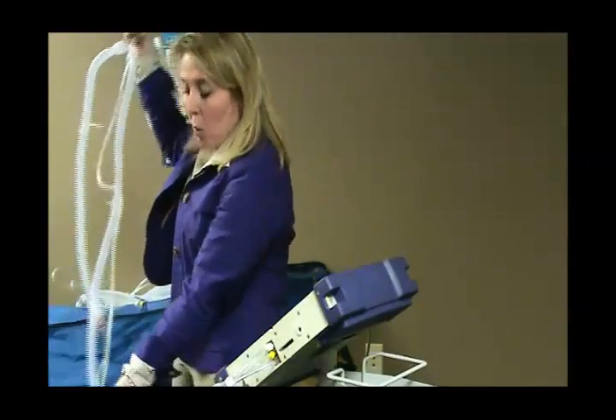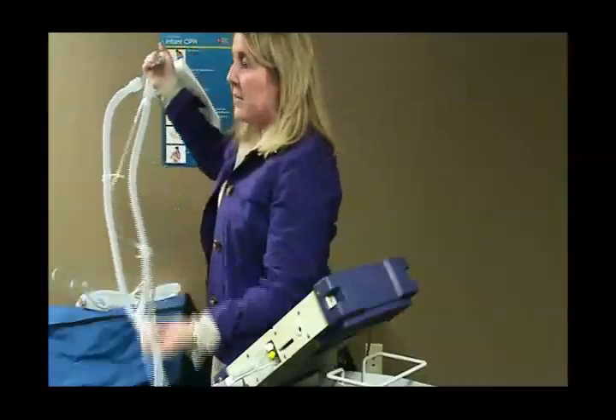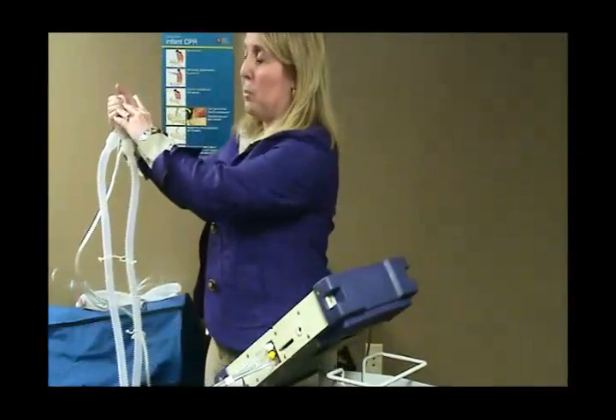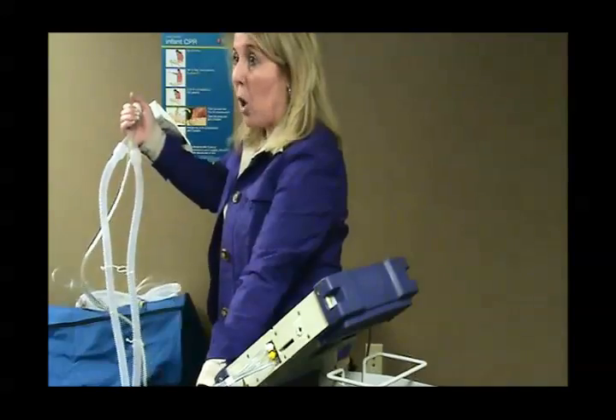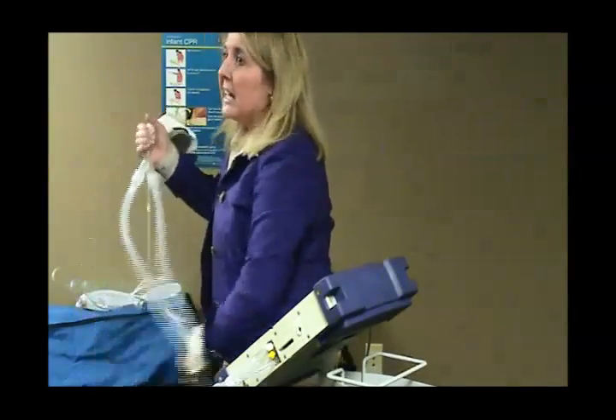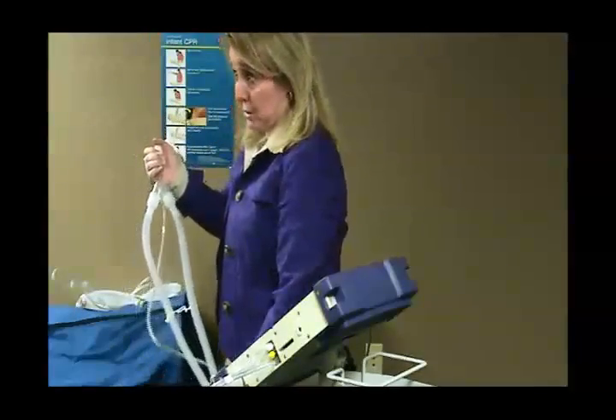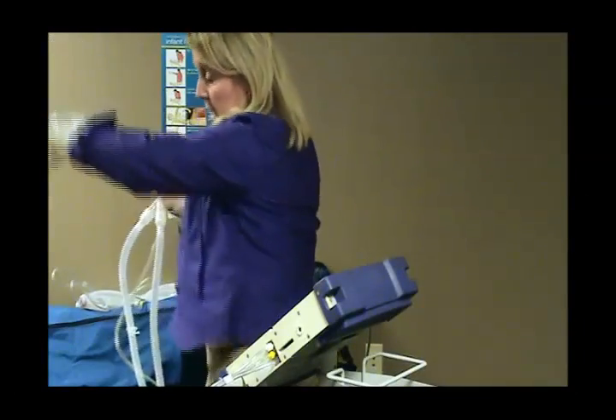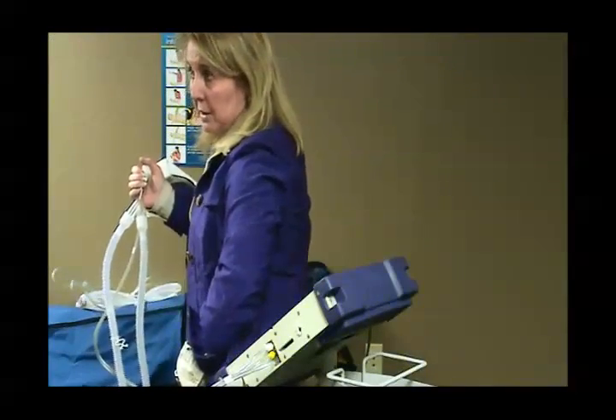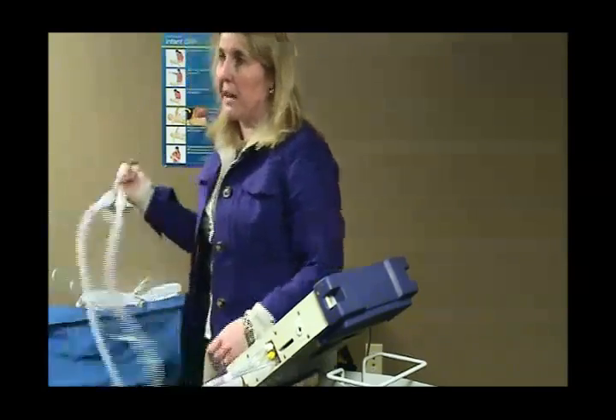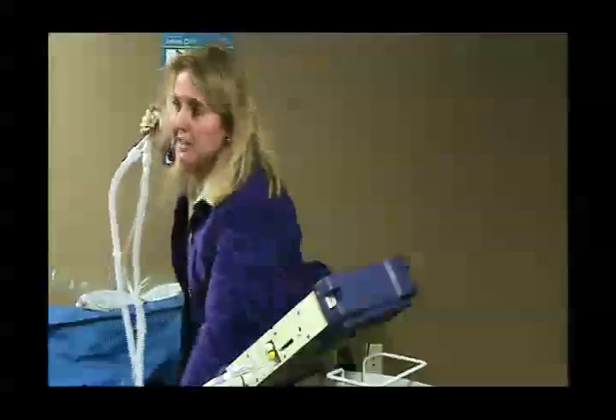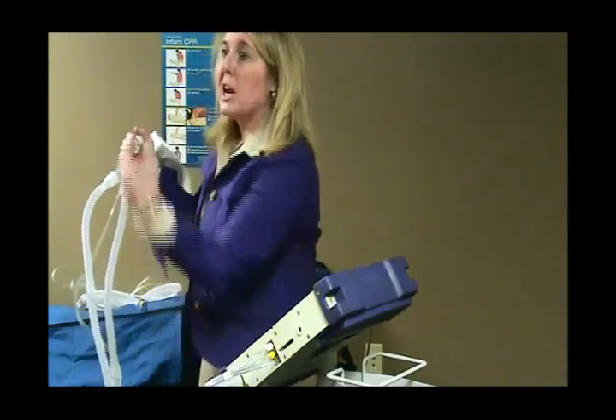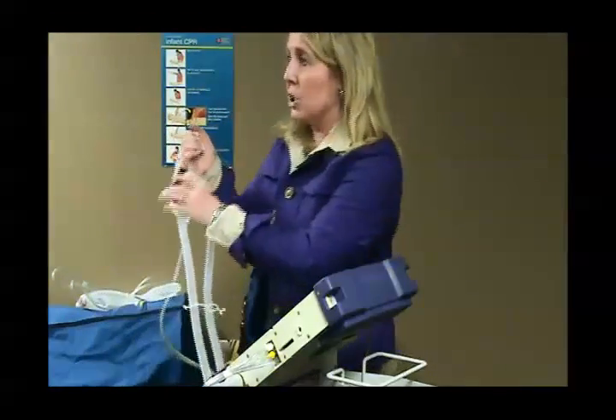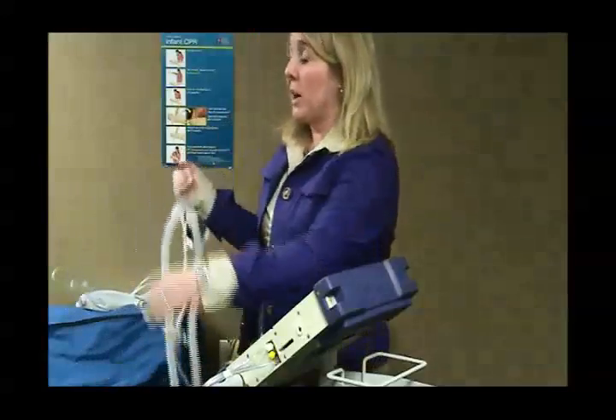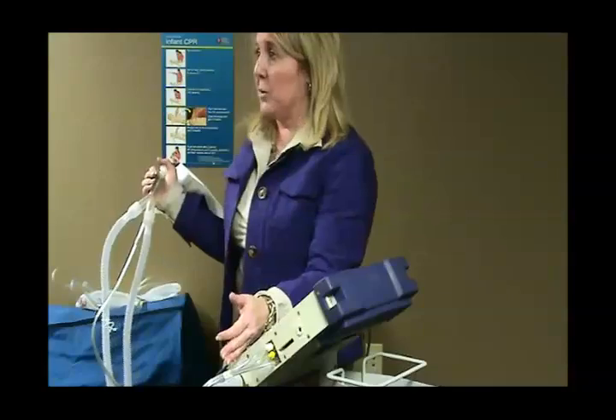So once in a while, you'll get a little water condensation build up in here. That condensation occurs because there's a temperature differential between the water chamber and the patient. Fanning it and shaking it makes it worse. Much worse. Having a fan blowing on it makes it worse. Moving the tubings around makes it worse. Why? Because those are all things that cool the circuit between the water chamber and the patient. So we want to try to empty those. We want to try to keep big giant temperature gradients between the patient and the heater from occurring.